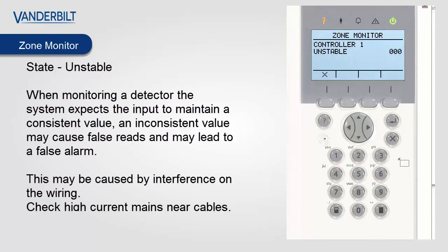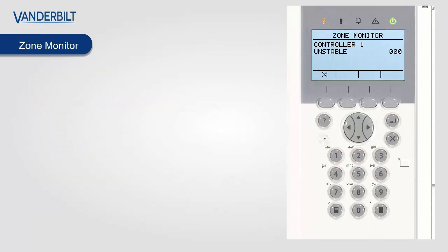Zone state unstable: when monitoring a detector the system expects the input to maintain a consistent value. An inconsistent value may cause false reads and may lead to a false alarm. This may be interference on the wiring — check for high-current mains near the cable or any other interference sources.